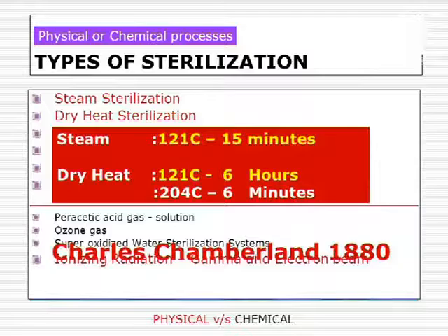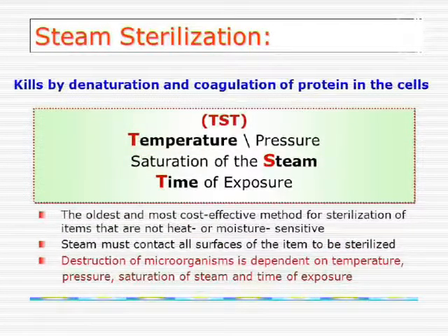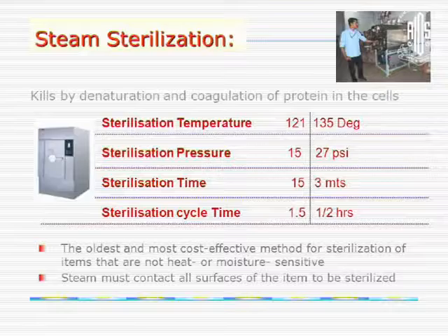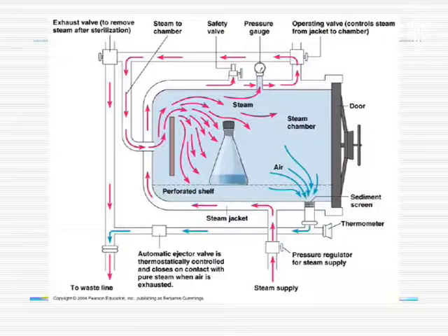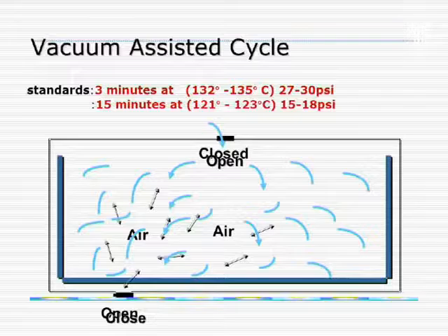There are three factors in steam sterilization: temperature, saturation of the steam, and time of exposure — all three are equally important. The parameters are 15 minutes at 121–123°C at 15–18 PSI, or 3 minutes at 132–135°C at 27–30 PSI. In autoclaves, the air must be removed completely before sterilizing. Whenever you buy an autoclave, ensure it has a vacuum cycle.